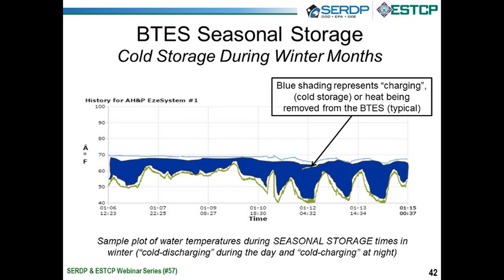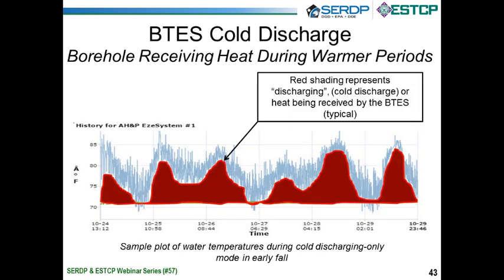As you can also see on the blue line, it is falling in time. So as the winter is going on, we could originally only give 70-degree water. Now we're getting periods where we may be giving 65-degree water. So that worked out well.